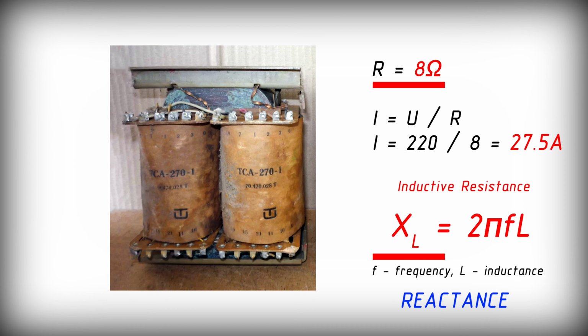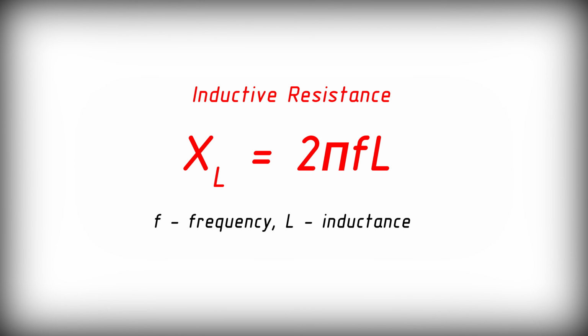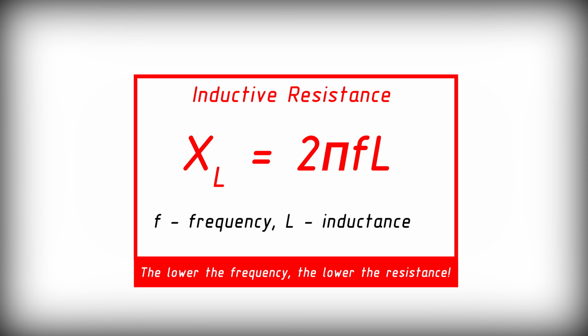It's important to understand that reactance also depends on the frequency of the AC. So if you have a transformer designed for a frequency of 500 Hz, you cannot connect it to a wall outlet, even if it's rated for 220 volts.